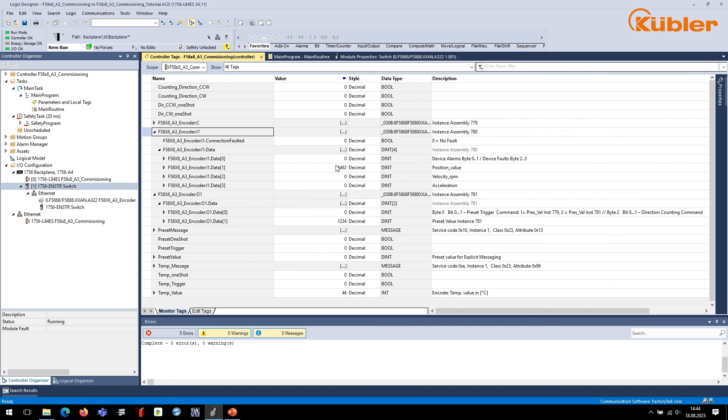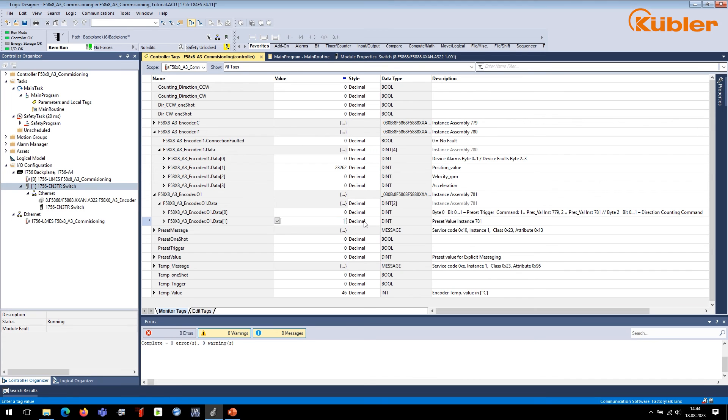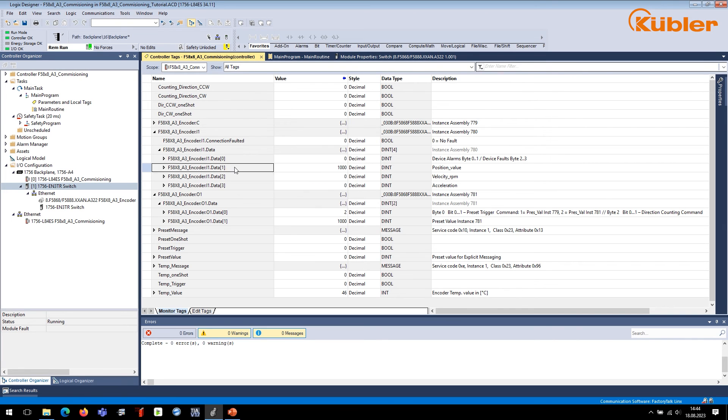First, make sure the preset trigger command bits in byte 0 of output assembly number 781 is set to 0. Then, set the preset value in the fourth byte of the instance assembly 781. In this example, we use the value 1000. Set the preset trigger command bits to 2. Right after entering the values, we can see that the position of the encoder jumps to the predefined preset value.